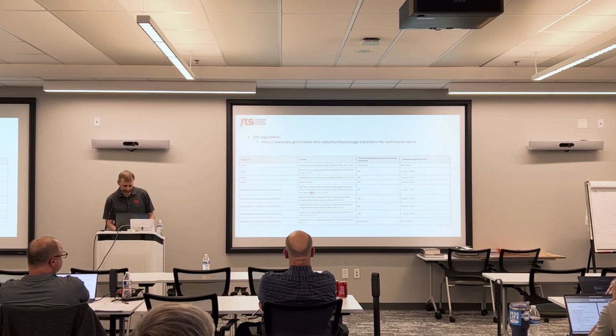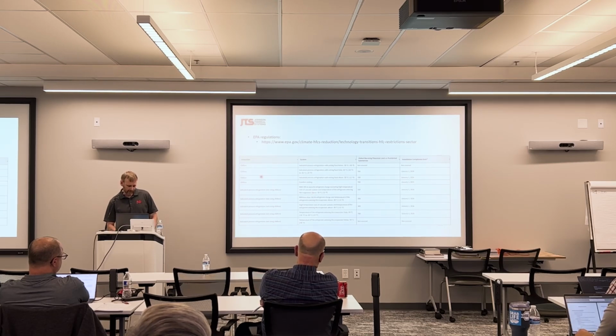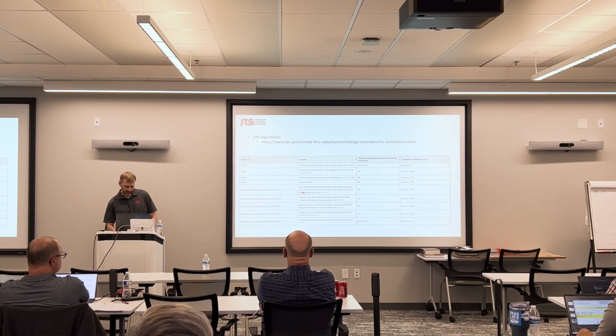So I'm going to switch gears on you guys a little bit and talk about this third wave that's coming through of refrigeration. According to the EPA, starting January 1st, 2026, we got some changes coming. Most chillers and air conditioners will have to be using refrigerants that have a GWP of 700 or less. Process refrigeration, if you're using more than 200 pounds of refrigerant, you have to have a refrigerant with GWP of 150 or less. If you have less than 200 pounds of refrigerant, you need a refrigerant with a GWP of 300.